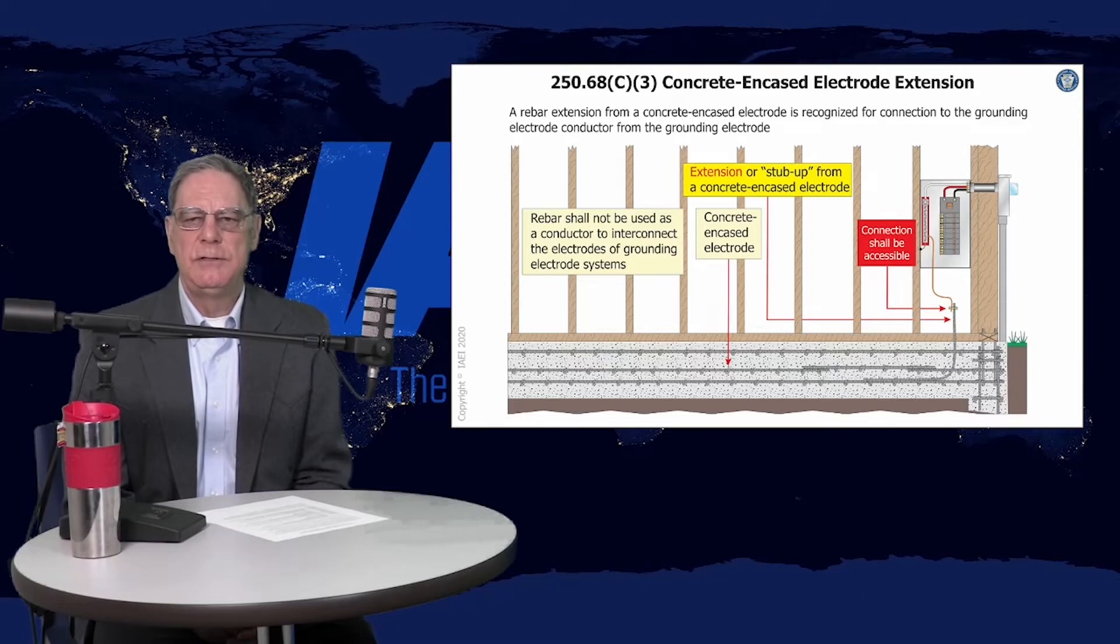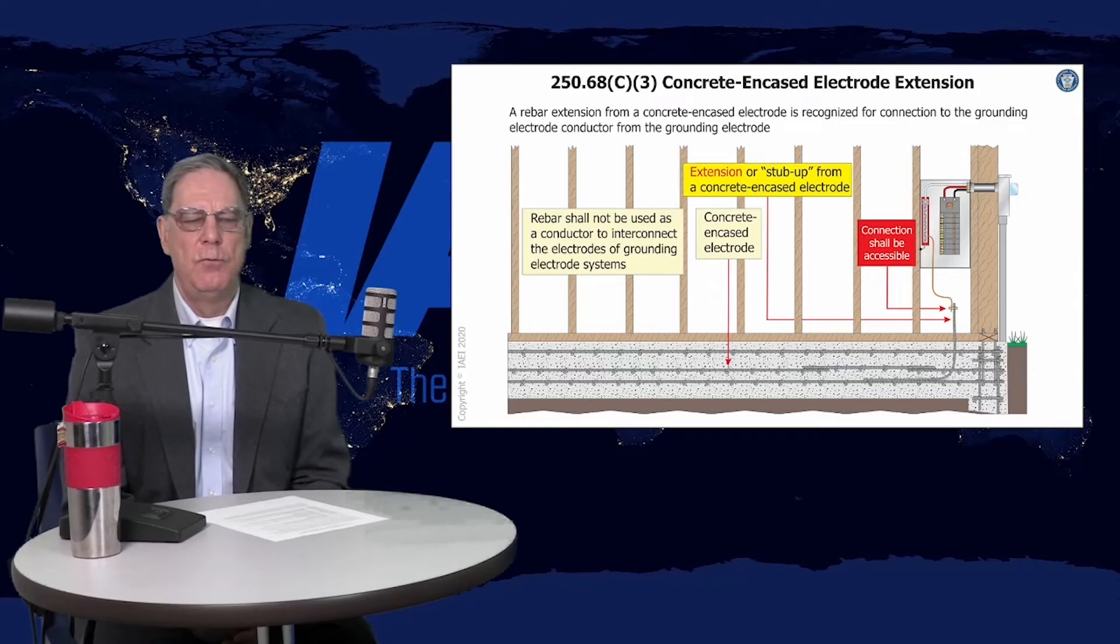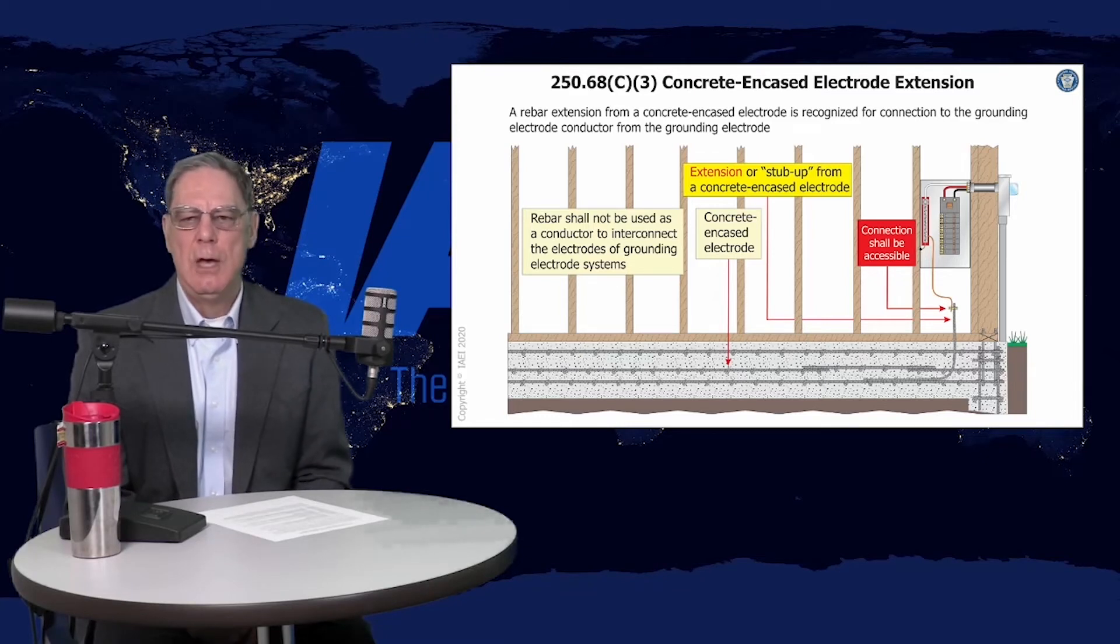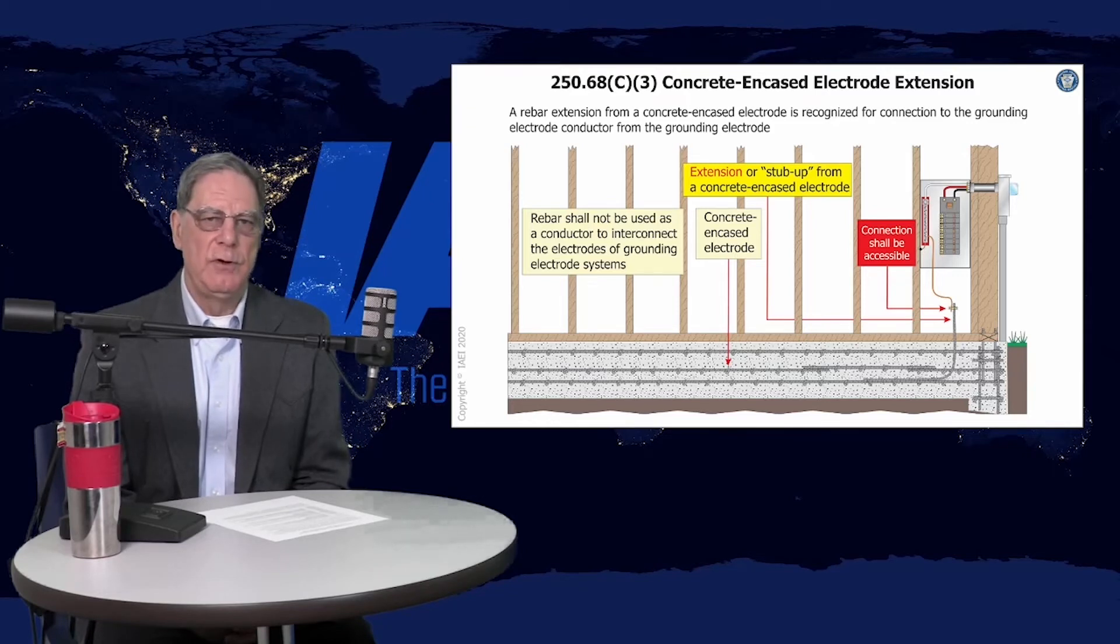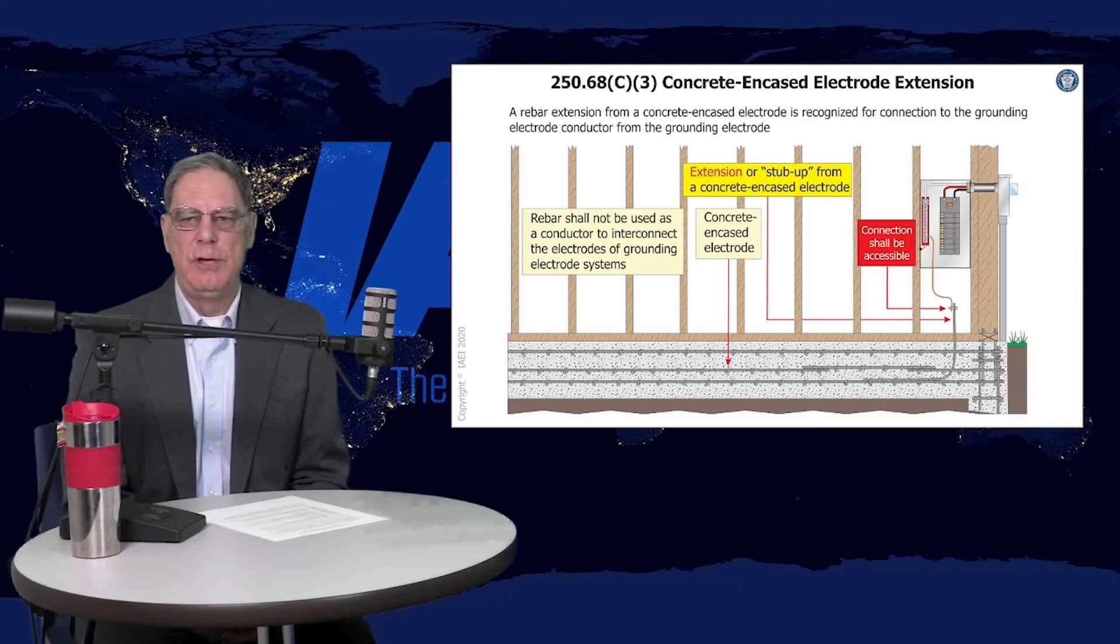One of the things you'll find common, and this came into the code a few cycles back, is having that rebar stub up. We used to say where the concrete encasement was available, it had to be used. The argument was, well, the foundation's already poured, rebar's already covered, it's not available. It's not really a good excuse, but it's an excuse being used. The code panel made the change to change the word available to present. So if it's present there in the footer foundation, it shall be used there.